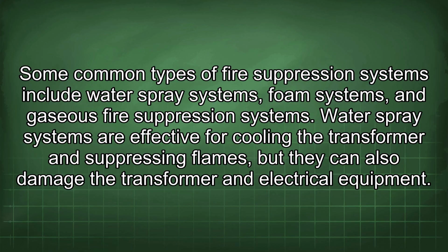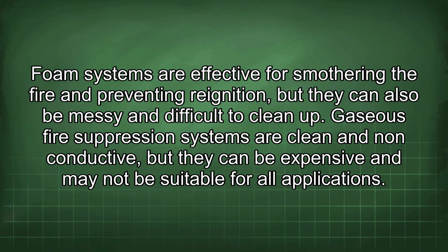Water spray systems are effective for cooling the transformer and suppressing flames, but they can also damage the transformer and electrical equipment. Foam systems are effective for smothering the fire and preventing reignition, but they can also be messy and difficult to clean up. Gaseous fire suppression systems are clean and non-conductive, but they can be expensive and may not be suitable for all applications.